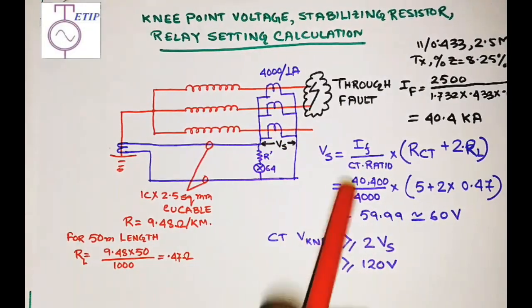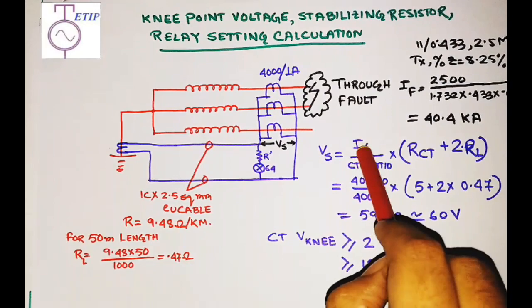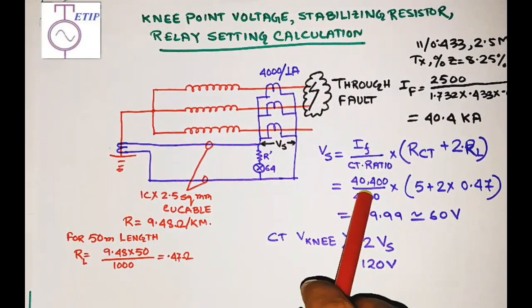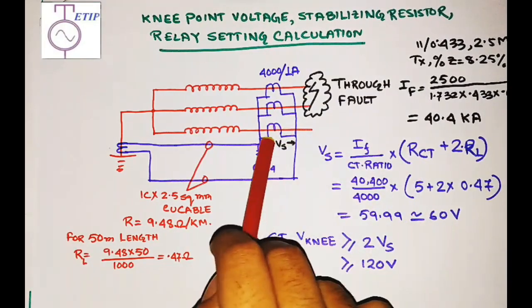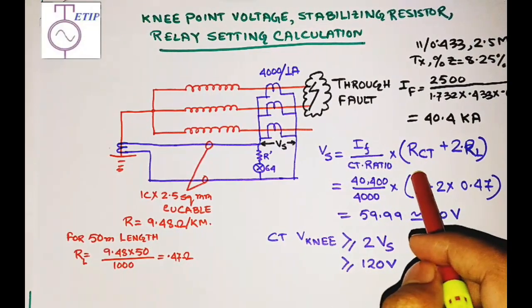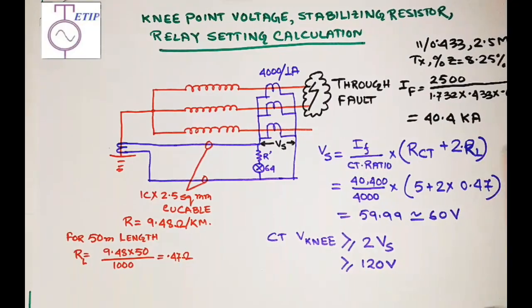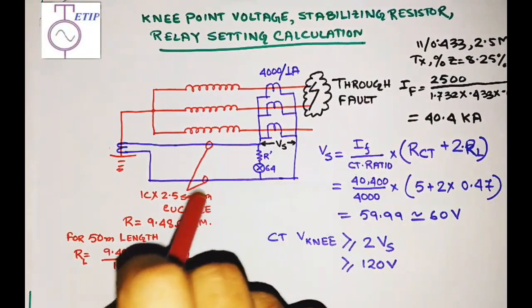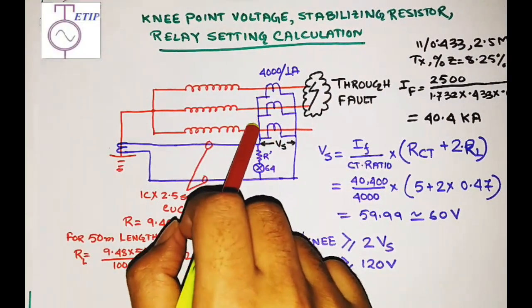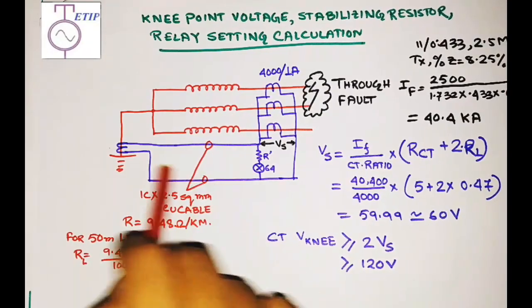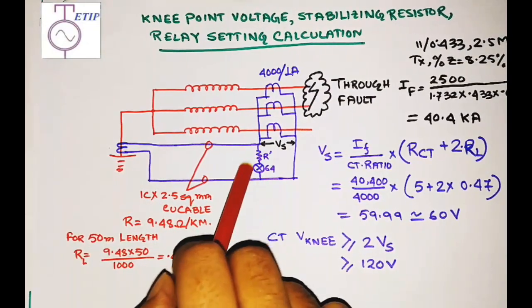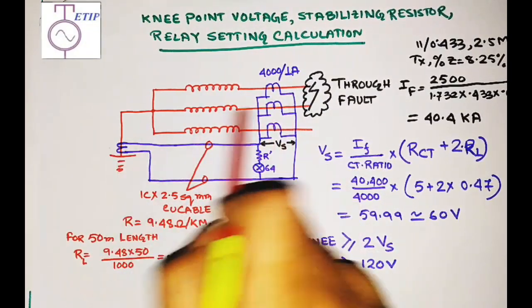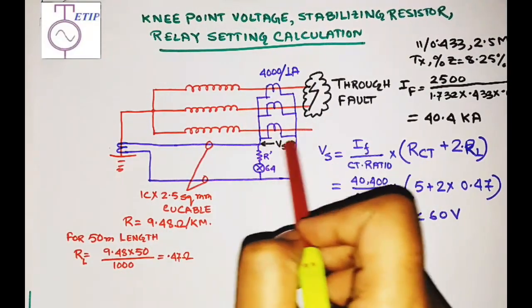Now, how do we calculate Vs? The formula is: Vs = (If / CTR) × (Rct + 2Rl). Here If is the fault current in amperes, and since this is a 4000/1 A CT the ratio is 4000. Rct is the internal resistance of the CT — this is a specified value, generally less than or equal to 5 ohm, meaning the CT resistance should not exceed 5 ohm. Rl is the lead resistance — the CTs are generally placed at the transformer line bushing or neutral bushing, but the relay is usually placed at the switchgear or relay panel, which is away from the CT.